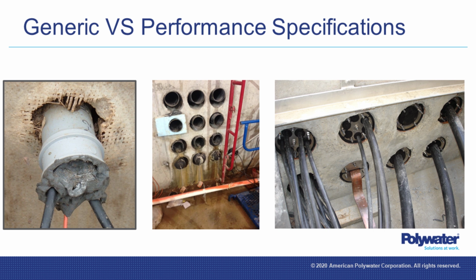and incidentally, it's the sidewall pressure that gets people into trouble more so than the ending tension on the cables. All cable manufacturers' sidewall pressures will differ based on the makeup of their cable, how they're built. It will also tell you what percentage of jamming could occur, and that you can only do on 3 cables. That's the way the math works. If you've got 1 cable, it's pretty easy to figure out. If you're pulling a 5-inch cable into a 4-inch conduit, you can't do it. But the software does all of that, and we have an excellent relationship with all the cable manufacturers. These manufacturers of cable are just outstanding.